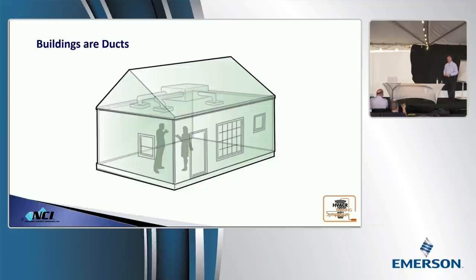Yes? You made a point earlier, when you were showing the slide about the 15 to 1 ratio, and I've got an issue that I've been dealing with where I believe the building is at negative pressure, not allowing the furnace to light with the fans running. Excellent. So the comment that was made was, Luke's running into a situation where you believe you're running into a negative pressure situation in a building, looking at the 15 to 1 ratio, and it sounds like you had an aha moment when you encountered that. But he thinks that 15 to 1 may be what he's dealing with, is combustion air is changing.